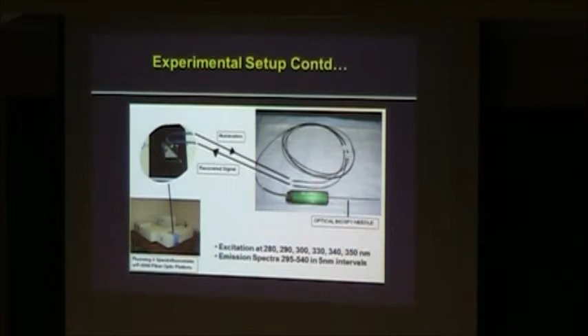So this is our old laboratory. This is this dinosaur here, a big Fluorolog 3 fluorometer, as I said, and we use this to excite the tissue at 280, 290, 300, up to 350 nanometer excitation. We actually captured the prostate tissue in the entire spectrum. After doing that, we sat down and looked at the data. We thought most of the interesting features are in this range, and the emission was picked up from 295 to 540. There was an optical bench here where we can pull the light. This is a 400 watt xenon lamp, and the detectors are photomultiplier tubes, PMTs. We pull the light signal out, it goes to the tissue, and then we return the signal back to the detectors.